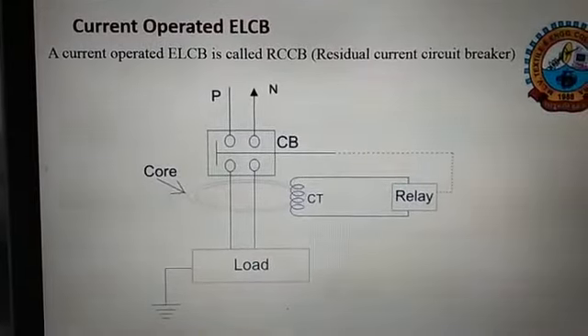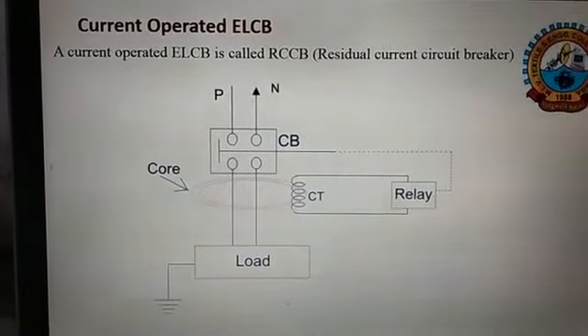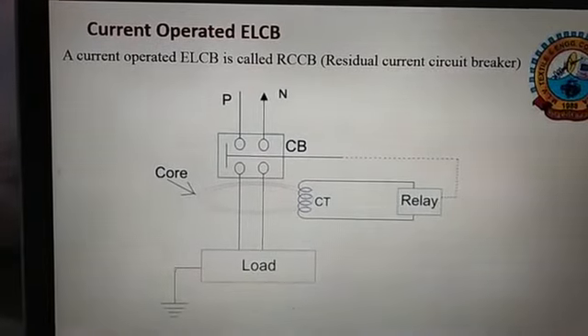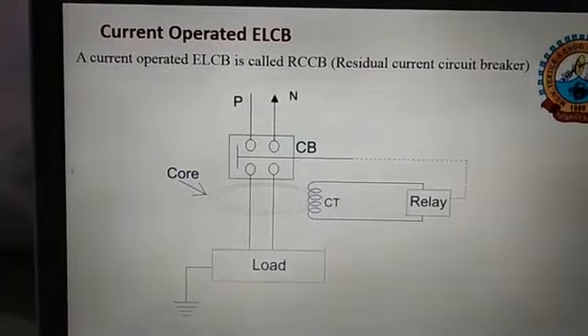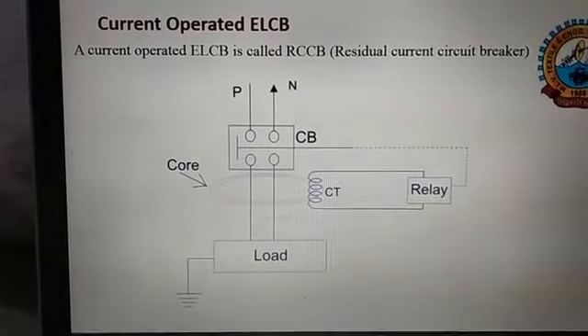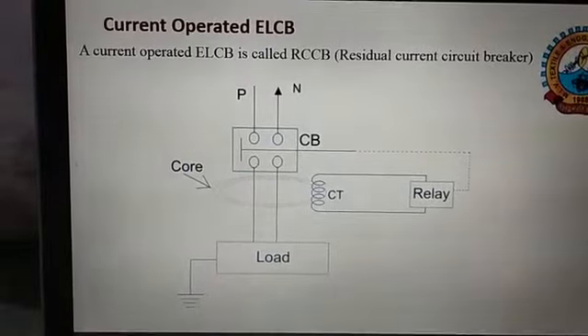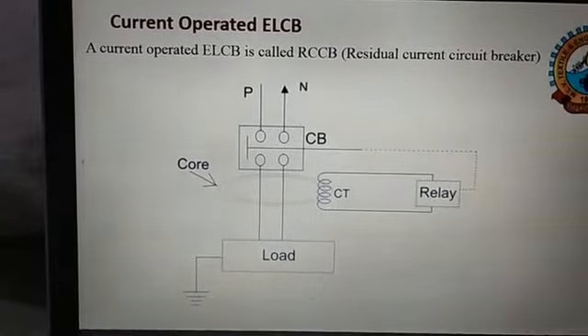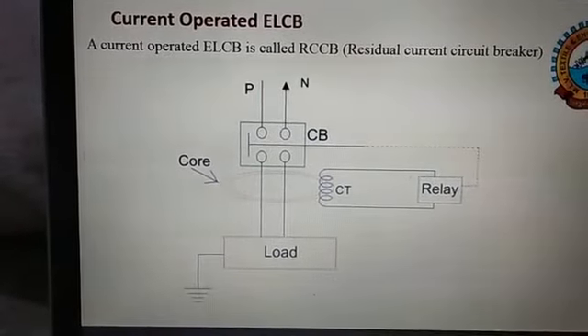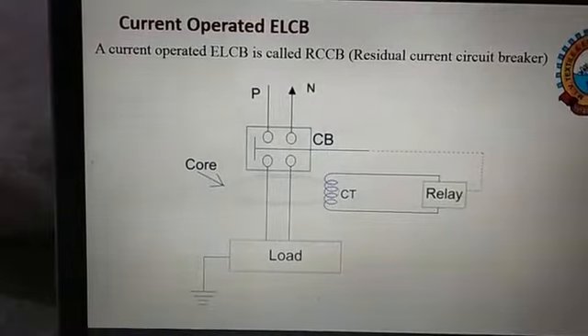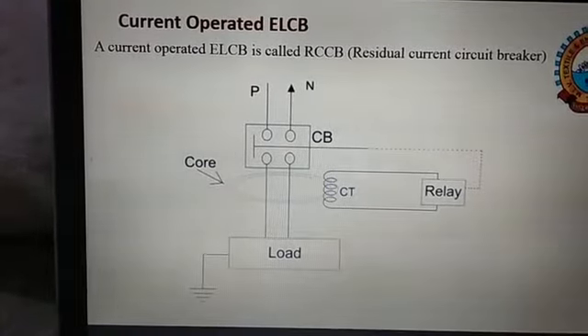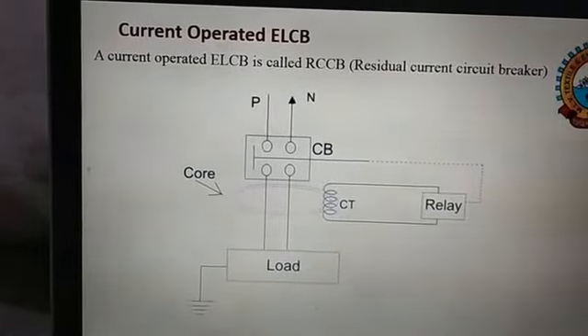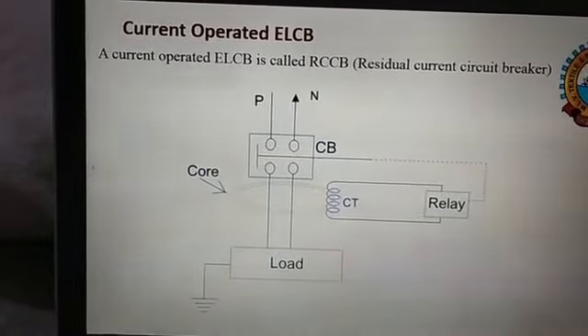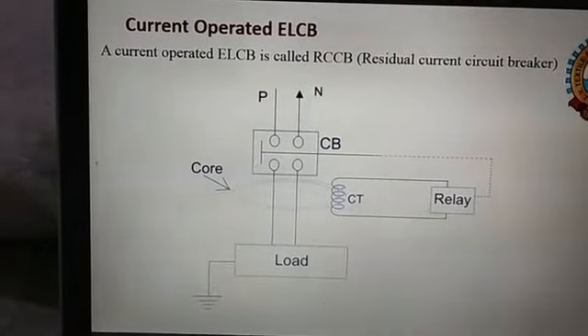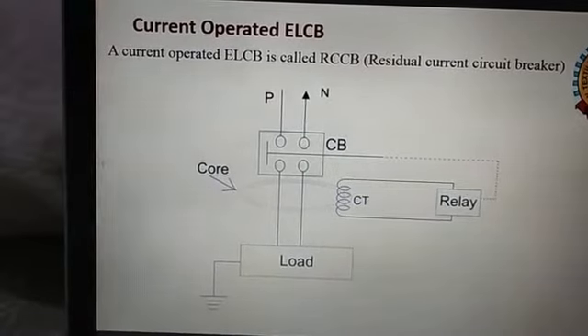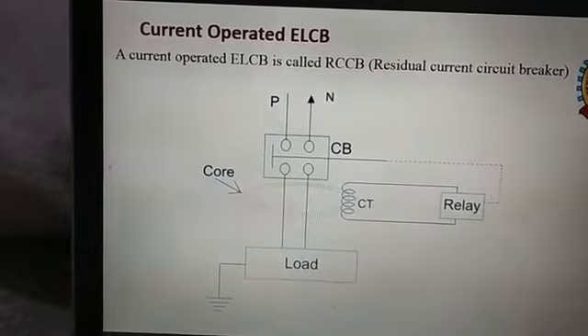The second type of ELCB is the current operated ELCB. A current operated ELCB is also called an RCCB, a residual current circuit breaker, which has a 3-winding transformer, 2 primary windings and 1 secondary winding. Neutral and line wires work as the 2 main windings. A wire wound around them forms the minor winding.